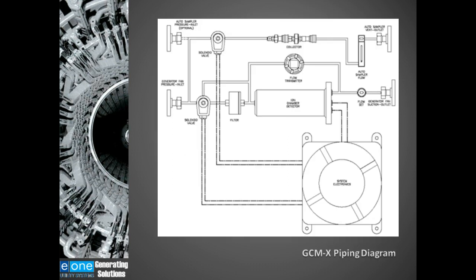This is a schematic of the GCMX internal piping. This unit shows a four-flange unit. You can see the flanges on the right-hand and the left-hand side. On the left-hand side, the bottom flange is the inlet. The hydrogen comes in that line from the pressure of the fan, bypasses the filter, goes around the filter through the ion chamber.